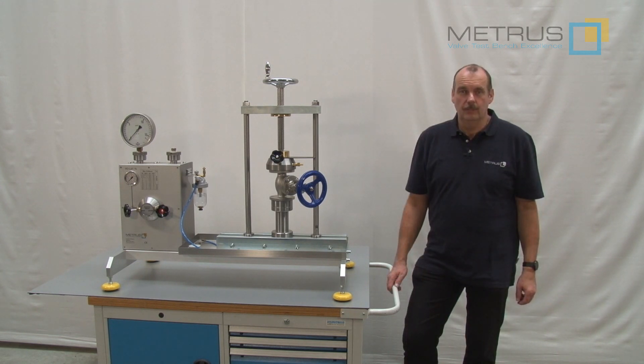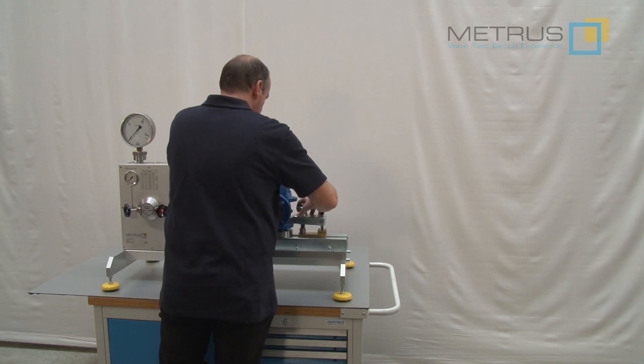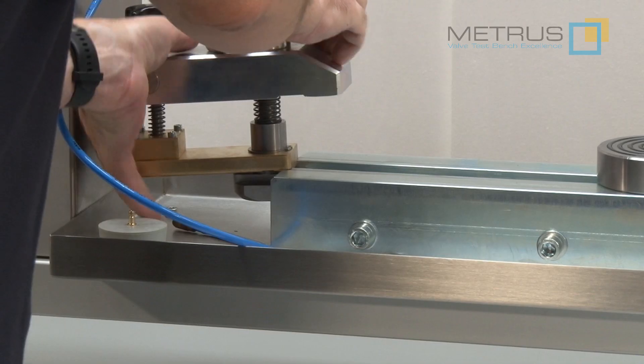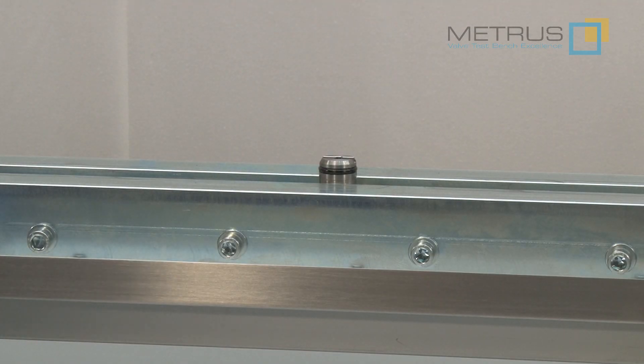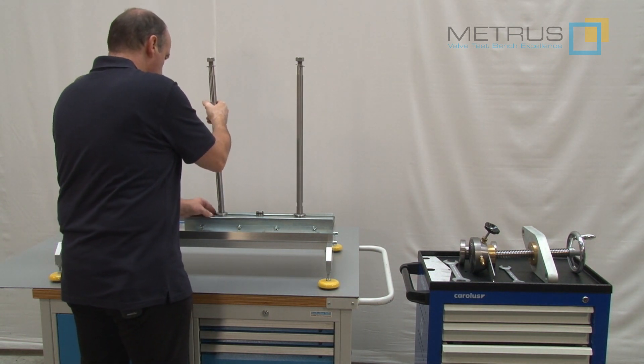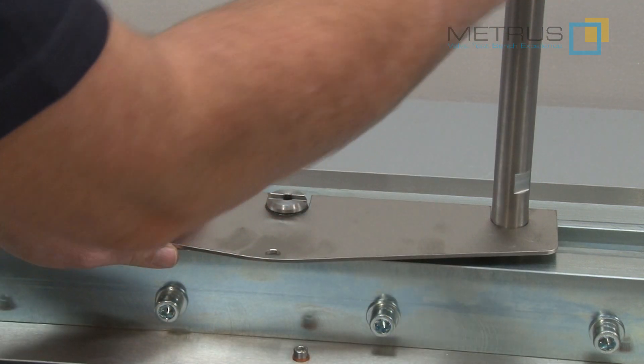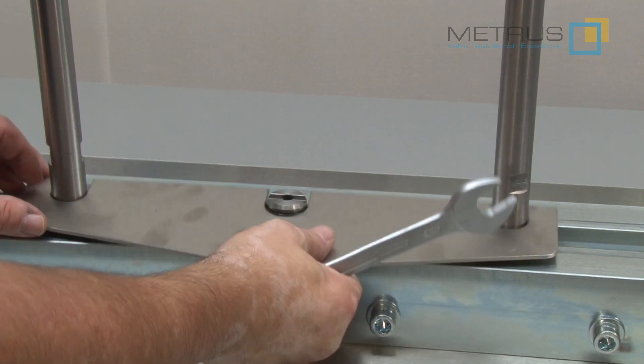I am going to show you now how to transform the SVM4100 into the E version. First of all you have to remove the clamping claw, then remove the O-ring sealing plate. Take the distance bolts and slide them into the slots where the clamping claws have been placed before. Now use the template to adjust the distance bolts to the center of the test bench. Tighten these firmly and remove the template.